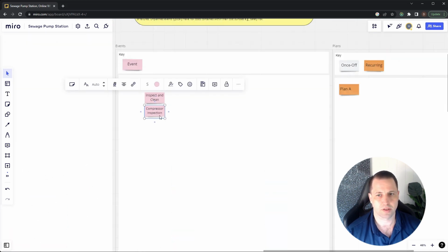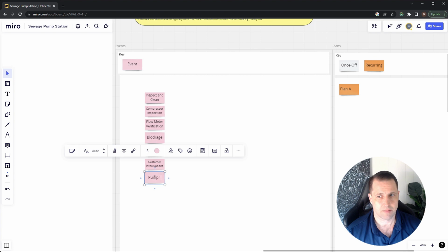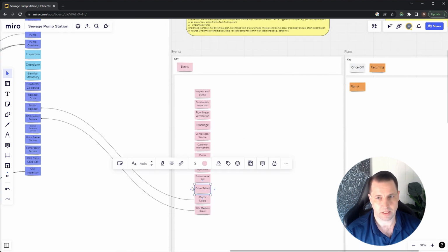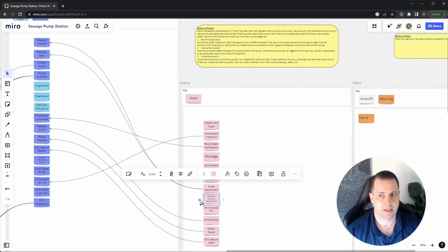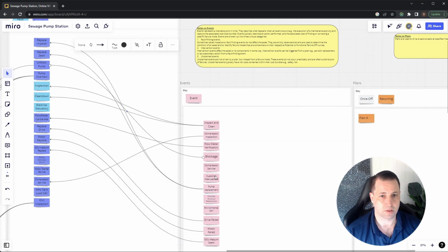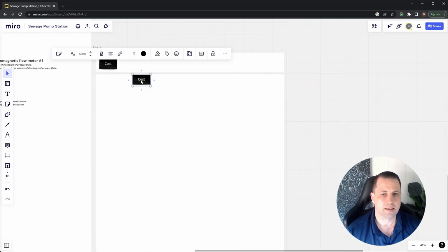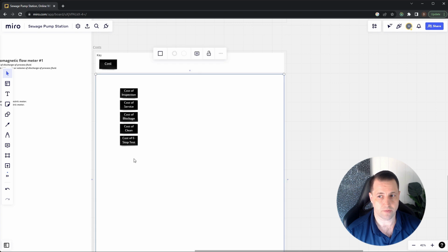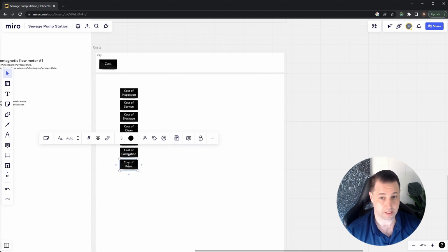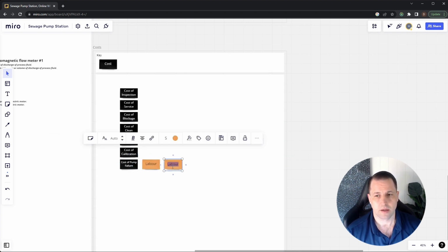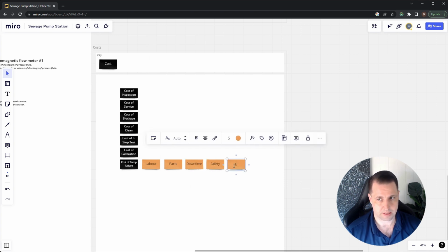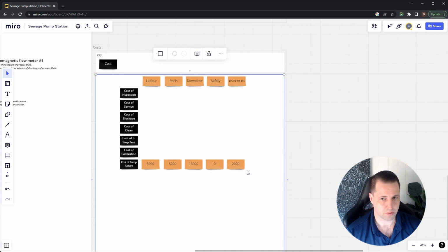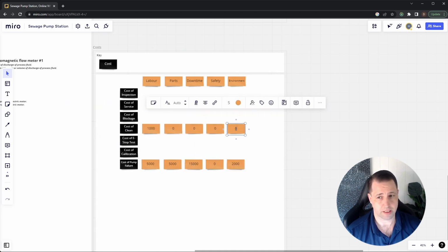We then look at the possible events and what we want to track, mainly failures and executions of plans. We link these events to the relevant failure modes, the relevant plans, the relevant costs, and the subsequent tasks. Next up is costs. Each event is given a default cost that can be either overwritten for each asset or contextualized using the inputs and causes. These costs can include labor, parts, and materials, but also things like monetized risk cost, for example, safety, stakeholder risk, environmental risk, etc.